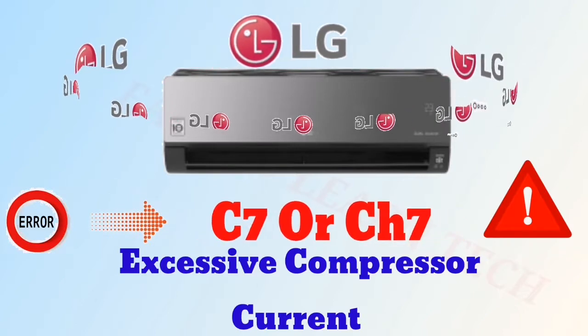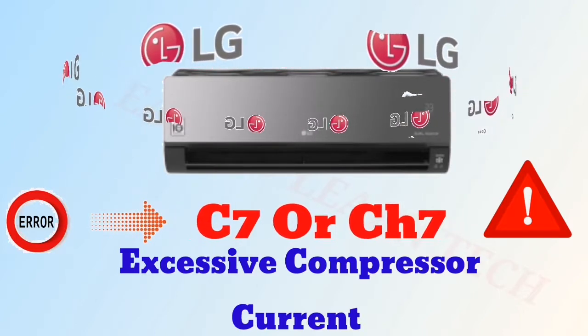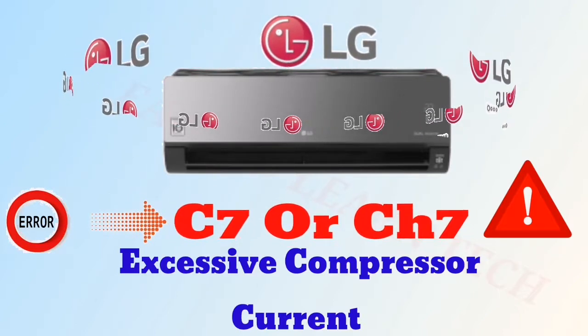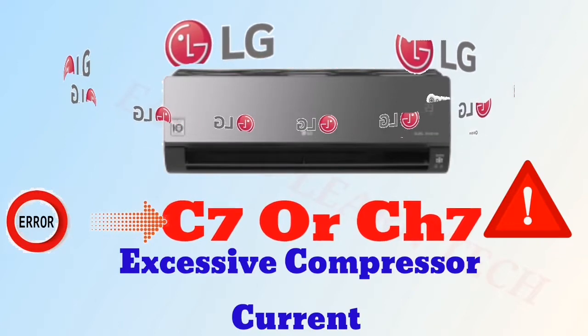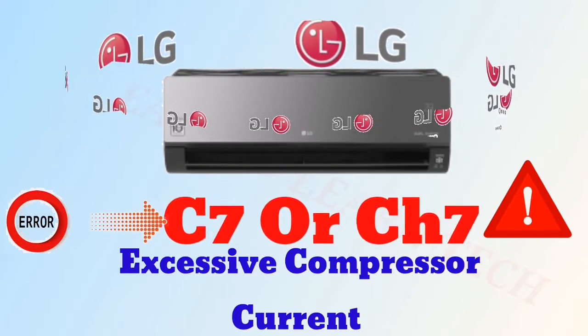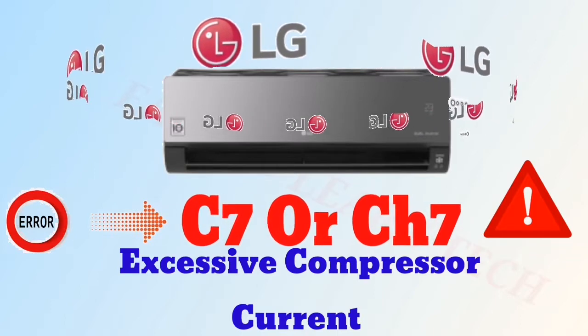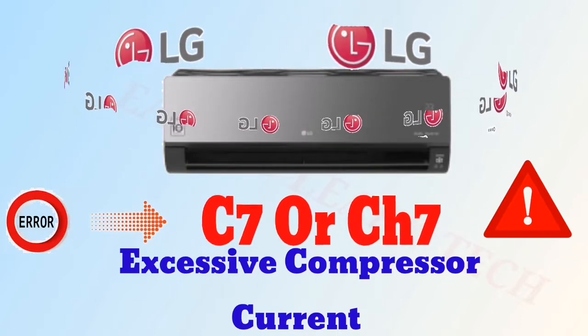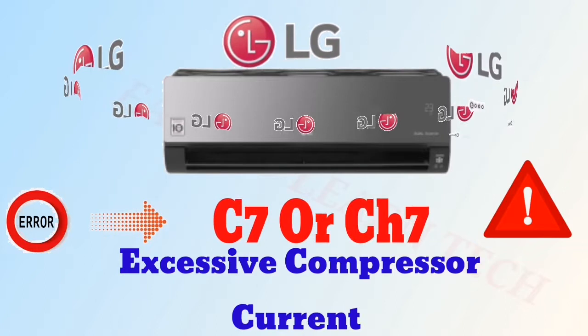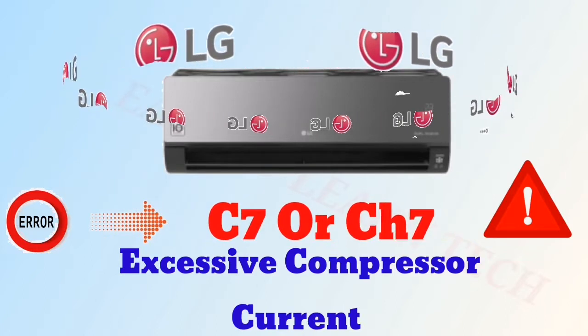And you have to check the filter of your indoor unit, as well as the condenser, if they are clear or not. If they are not clear, do the servicing and you will not get this error again. If you do this and you are still getting this error, it means the compressor itself is faulty. You have to check the continuity of the resistance and you have to check the ground of your compressor.